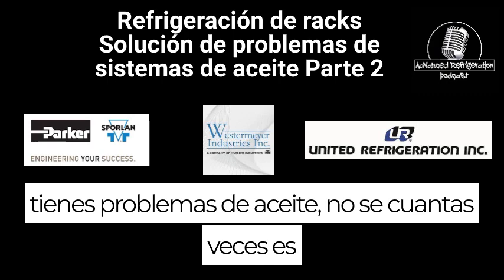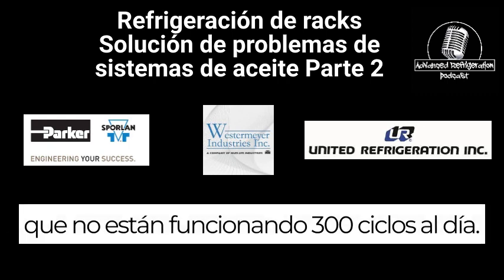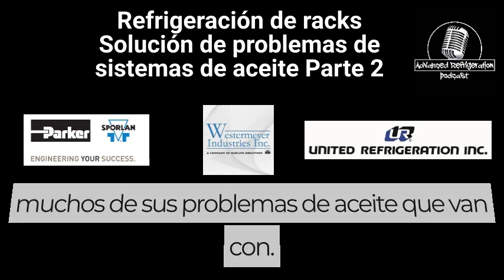I don't know how many times I've been behind guys and they're there for oil trips and there are compressors that are not running, or cycling 300 times a day. By the time you get that taken care of, a lot of your oil issues will go away.